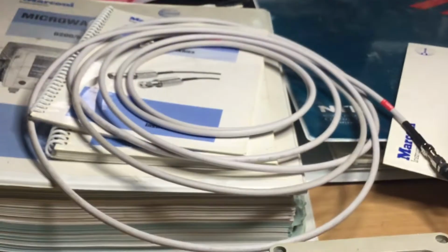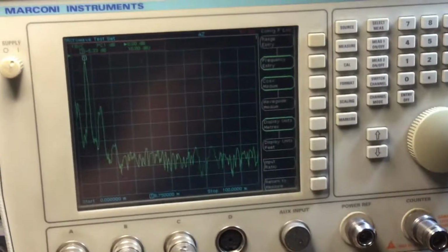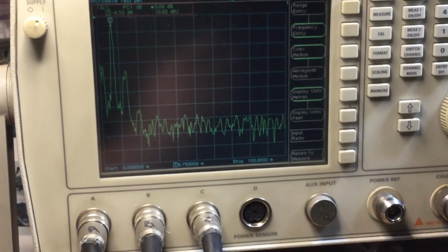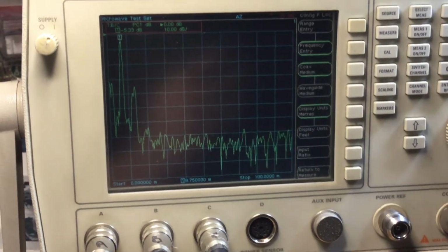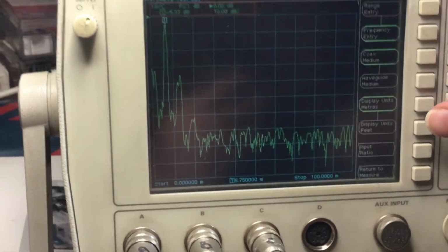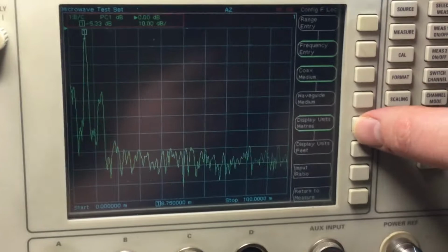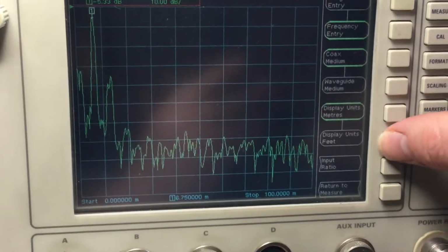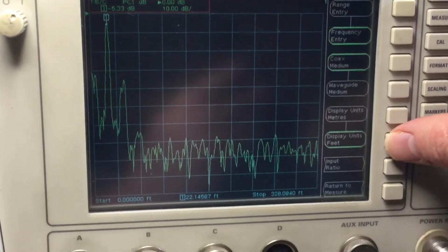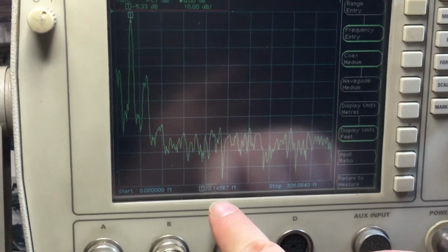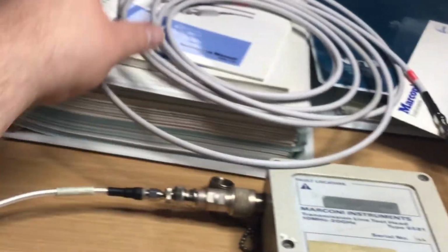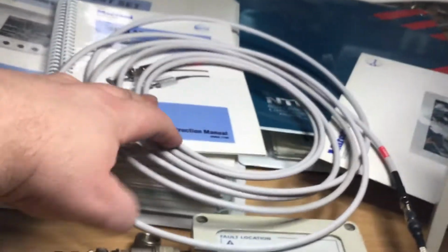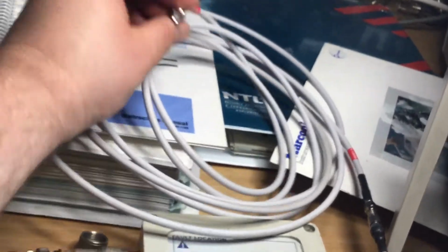But at the moment we're just using standard coaxial cable, this bundle here that I've piled up. So we're using a lower frequency of about a gigahertz, roughly. We can display in meters or in feet, and it will tell us where the fault lay, because we've got 6 meters of cable, plus this meter added, making it 7, and we've got an open end.